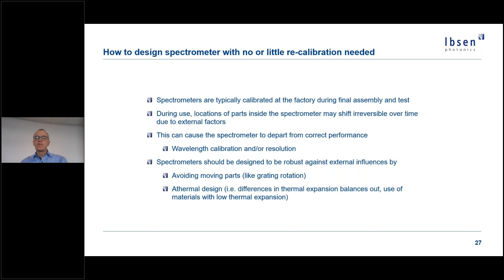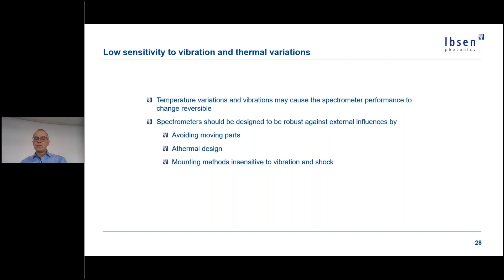A little bit along the same line, we also don't want the spectrometer performance, such as resolution, to change during operation, even if the change is deterministic and the spectrometer comes back to the original performance. The way to avoid this is by avoiding moving parts, designing the spectrometer to be athermal, and also to design mounting methods of components like the grating and optics to be insensitive to shock and vibrations.